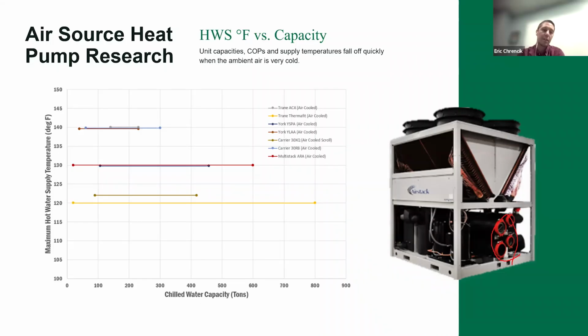We're looking at it now at SUNY Binghamton. So I see Andy Jones here. It's something that he analyzed at a high level, and the idea, assuming that project continues to move forward, would be essentially an ambient loop with a bunch of air source heat pumps at the plant level, and then some water-to-water heat pumps at the building level, and then you run your ambient loop at wherever it needs to be, 60 to 90 degrees or something along those lines. While that's different from what we looked at for UMass, it's a way that you can add heating at a greater COP, especially when you drive that hot water supply temperature down. You can generate your heating via an electric means with a higher COP than, for example, an electro boiler running at a COP of 1, or gas-fired equipment running, like Bill said, 80% or something along those lines, depending on the technology that you use.